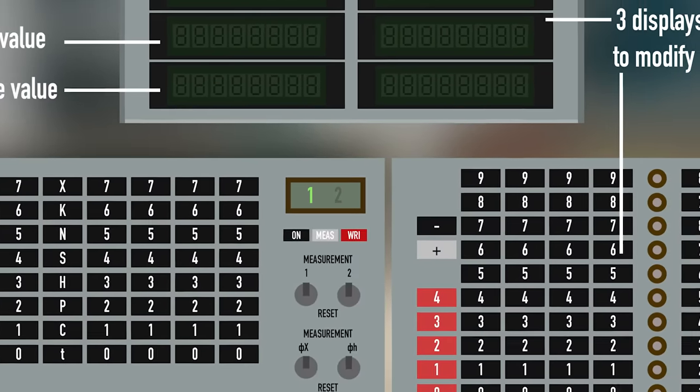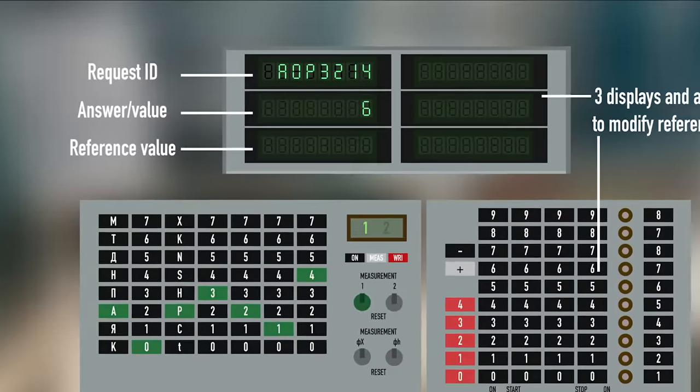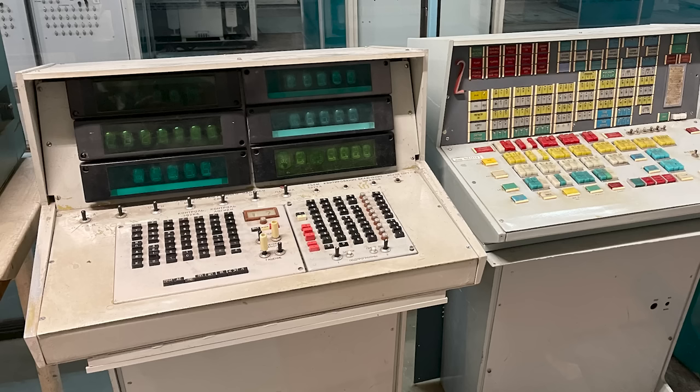For example, you type AOP3214 — where A stands for the reactor, O for general, P for pressure, and 3214 is a code reference inside the SKALA namespace. You send it to the machine using a toggle switch; it appears on the upper indicator, and on the bottom one you have the response value — for instance, 6 kilograms of force per square centimeter. It reminds me of the DSKY onboard computer of the Apollo spacecraft, because it had a verb-and-noun system which is somewhat similar. The computer engineer-in-chief uses this request device to retrieve various data, manage reference values, software, and system integrity.